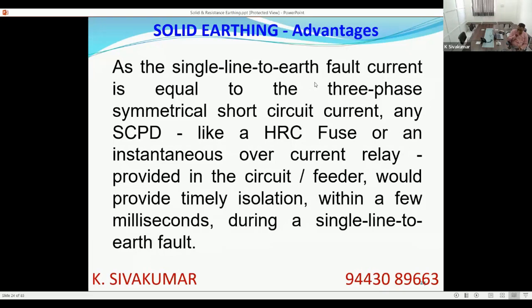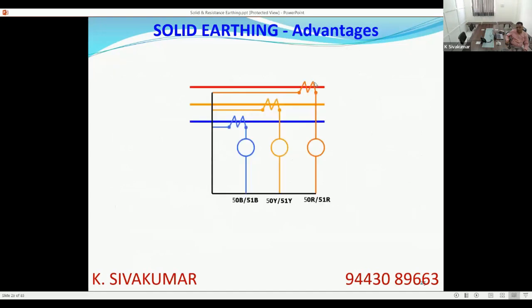If you take a case of a fuse, for severe faults, the fuse operating time is less than 10 milliseconds. Even sometimes good fuses are there which operate below the current peak, in 5 milliseconds they operate. So the fault isolation can be very, very quick, before it harms a person or harms a system or installation. Isolation is possible. So the protection can be something like this.